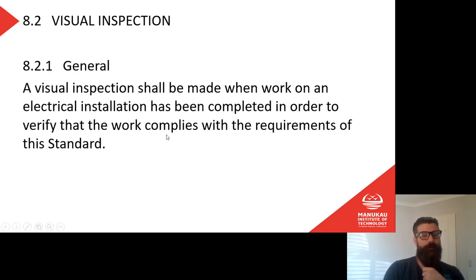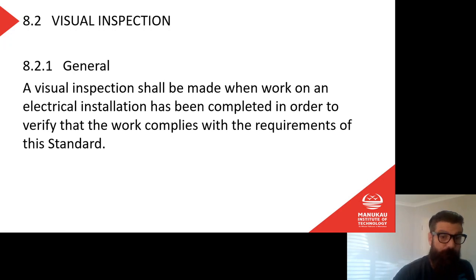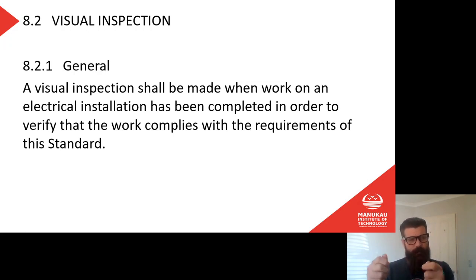Section 8.2, visual inspection. A visual inspection shall be made when work on an electrical installation has been completed in order to verify the work complies with the requirements of the standard. So visual inspection is exactly what it says. Go and have a look. It may not sound like testing, right? Testing is something that we do with meters and we get results and we write them down and it's all very clever. But a visual inspection, in a lot of cases, is probably our most important one.